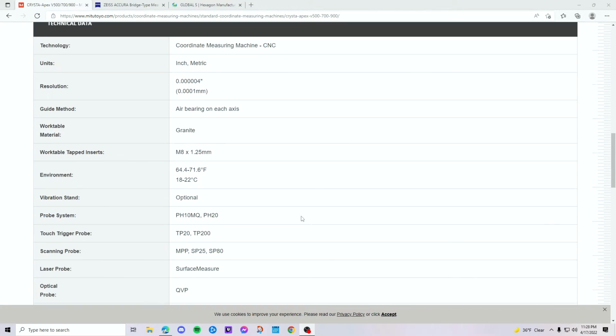And the wonderful thing about CMMs is the resolution that you get off of them. Now, this one is equipped with a Renishaw probe system, so you are slightly limited to that, but your resolution is in the fourth decimal place for metric, which is a tenth of a micron, which is extremely tight. The downside to CMMs is they generally need to be within a certain environment. There are exceptions to that rule, of course, like shop floor CMMs, and a lot of times you can run something called temperature compensation to correct that.